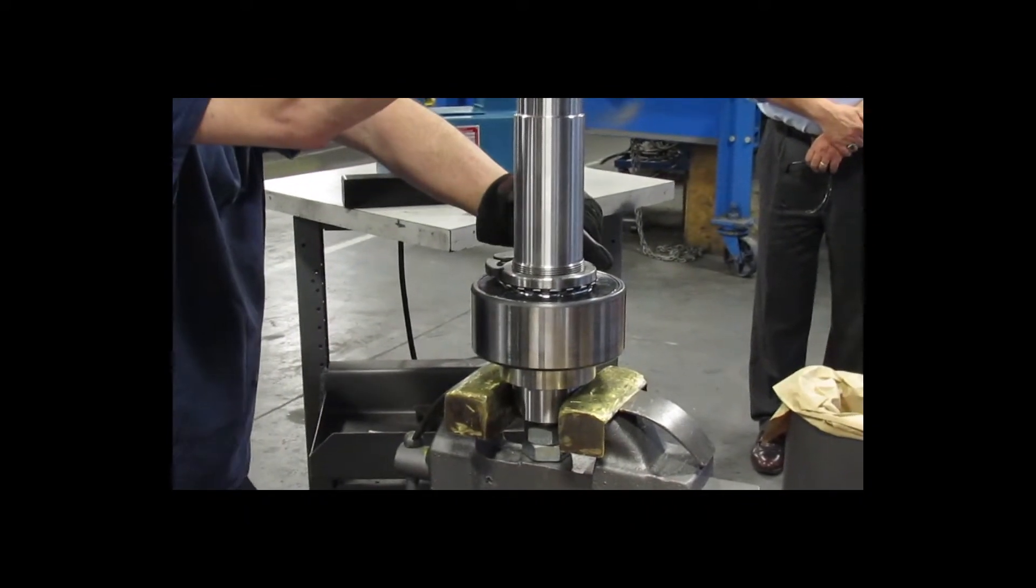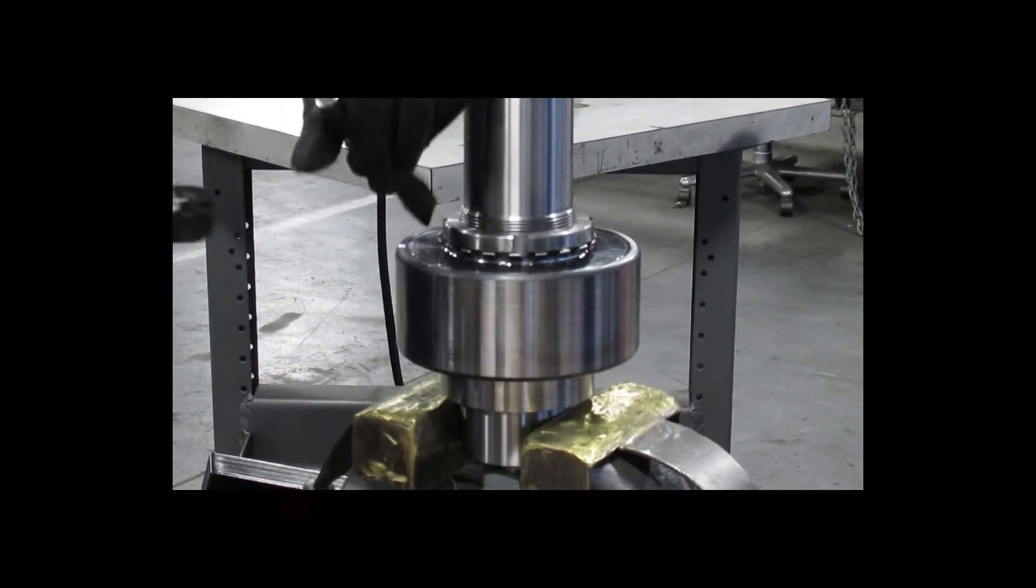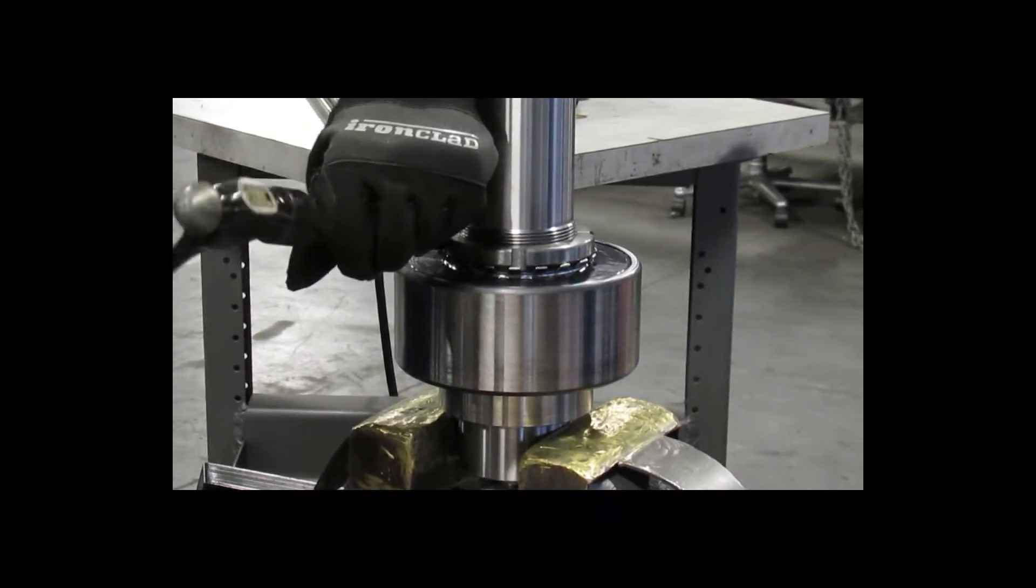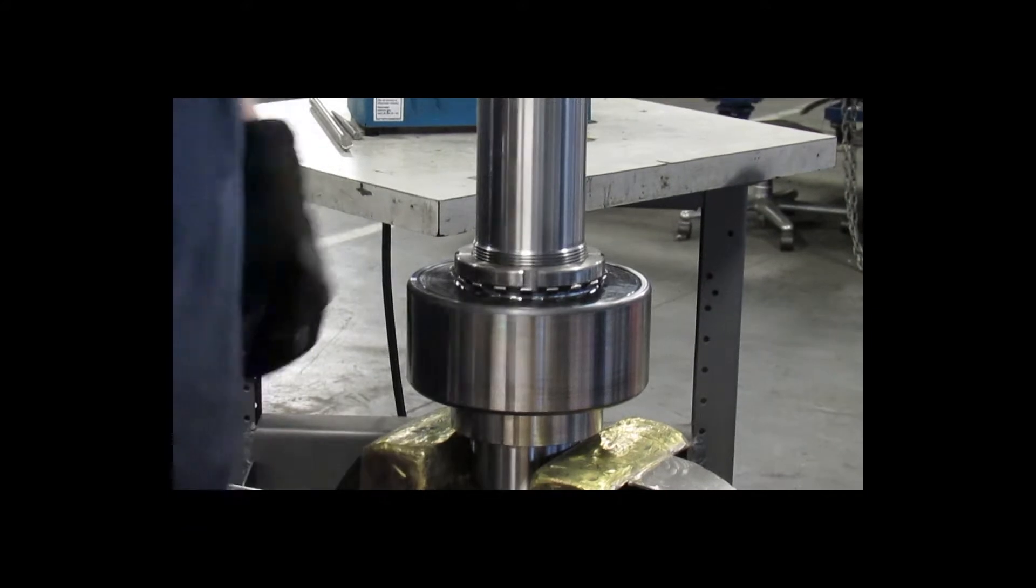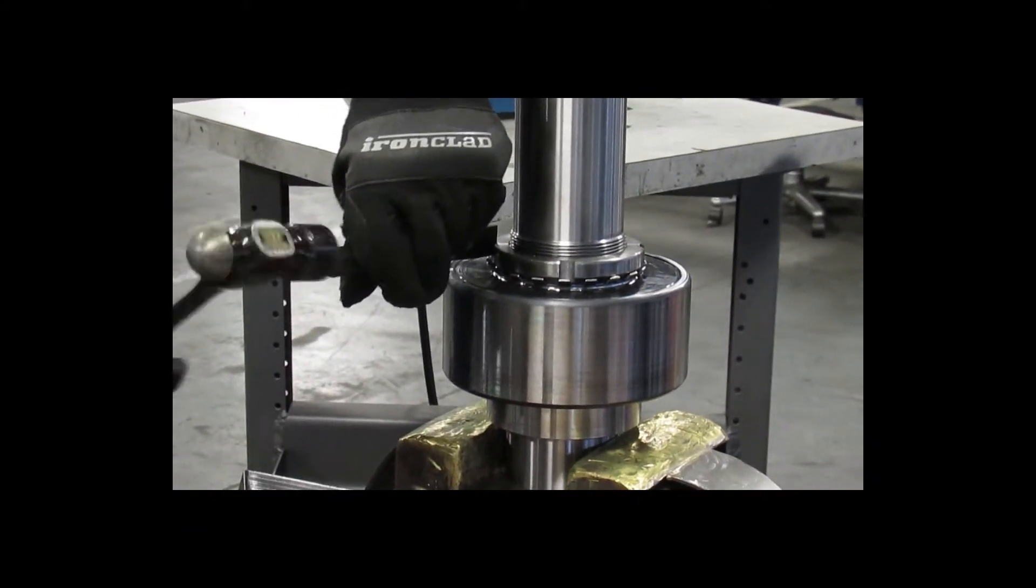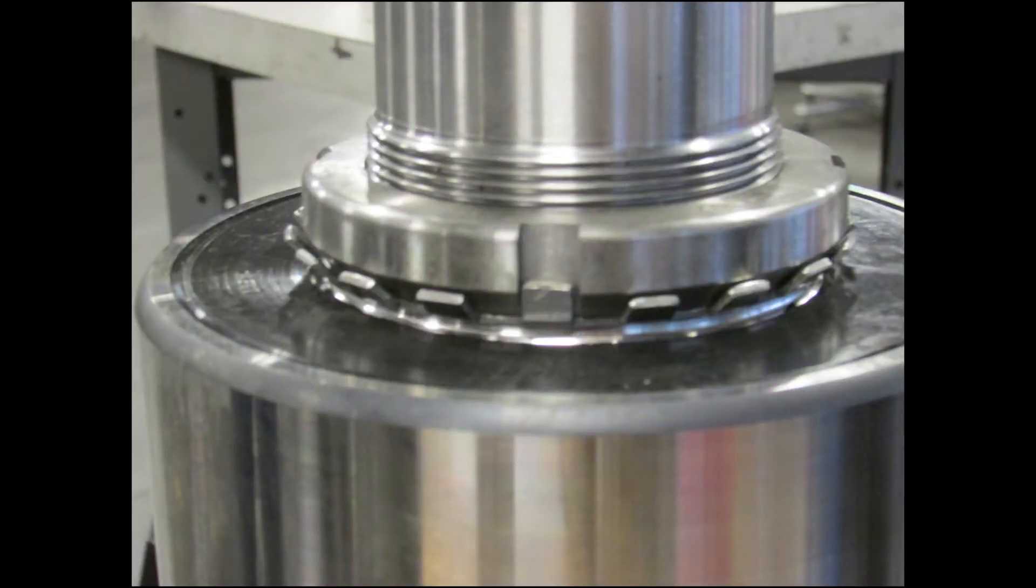Often times, it is necessary to use a spanner to secure the lock nut. When one of the tabs on the lock washer is aligned with an opening on the lock nut, a drift and a hammer can be used to knock the tab into the opening, securing the lock nut.